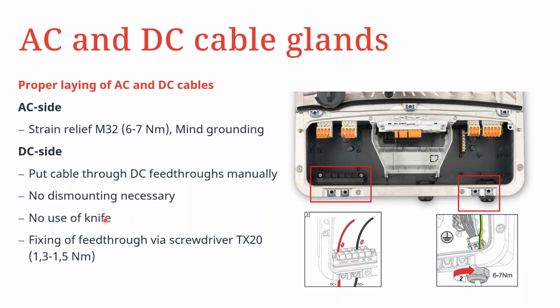And you are also not allowed to use knives for making perforations for connection of the cables. So you can insert the cable directly into it, and that ensures that there is enough closing of the cable gland around the DC cable. And for the 2 screws at the top here, we only allow 1.3 to 1.5 Newton meters for tightening that strain relief for DC cabling.